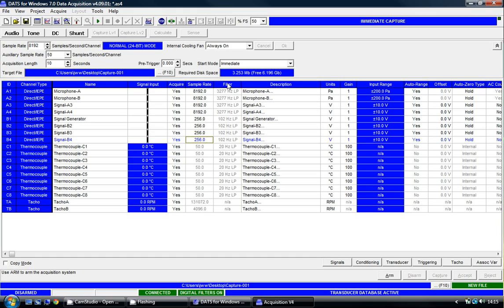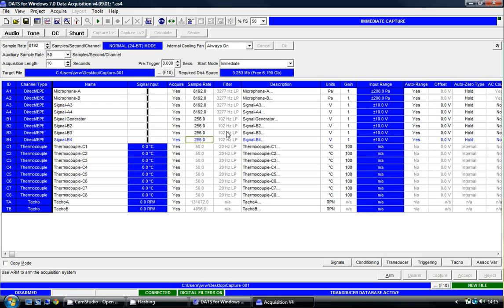The filter column shows you the bandwidth available for each particular channel. For the first four channels, we have just over 3000 Hz of bandwidth. For the second four channels, we have just over 100 Hz. And for the eight thermocouples, we have 20 Hz of available bandwidth.